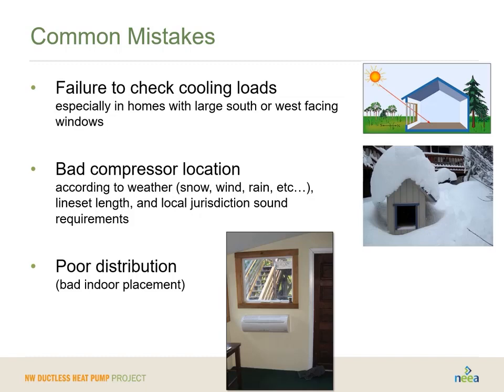There are several common mistakes in how these things are designed and selected. The first is forgetting to check the cooling loads. This is really important if you've got homes with a lot of large south and west windows. You really do want to make sure you're actually doing the cooling loads as well. Some of that simple rule of thumb sizing doesn't really get you there, but engineering tools will.